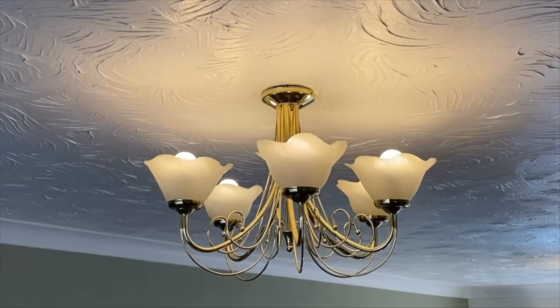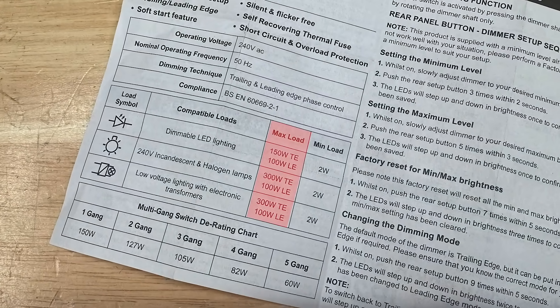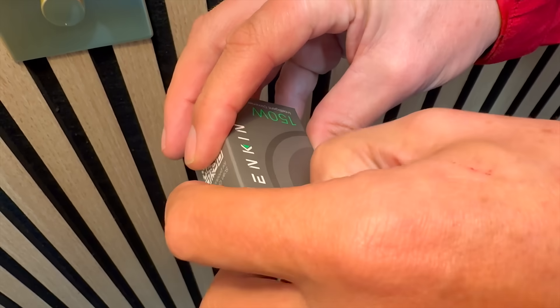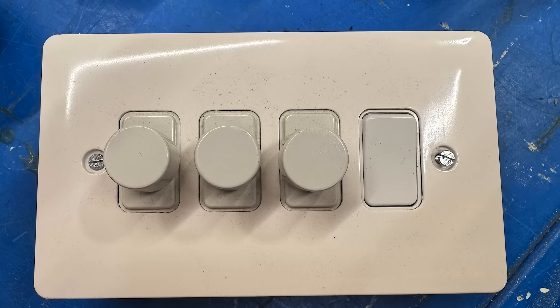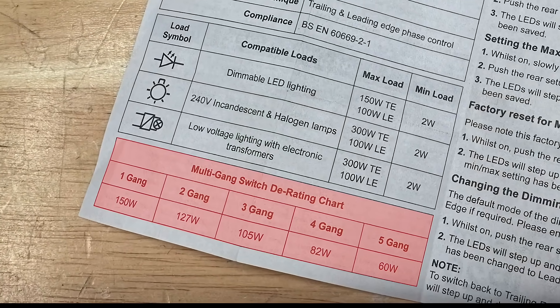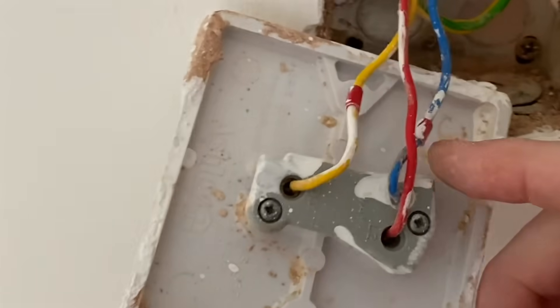If you don't meet the minimum load, the dimmer may start to misbehave — you'll see flicker, instability, or the lights might not dim properly at all. Dimmers also have a maximum load, and that can vary depending on whether you're using traditional lamps or LEDs. Maximum loads for LED circuits are usually lower, because the electronics inside the dimmer are doing a lot more work to control those small fast-switching loads. This Enkin dimmer is rated up to 150 watts of LED load — plenty for most installations. But if you've got multiple dimmers fitted in the same enclosure, they'll all generate heat, and you may need to derate each dimmer slightly. These dimmers are also fitted with a self-resetting thermal fuse and built-in short circuit protection.